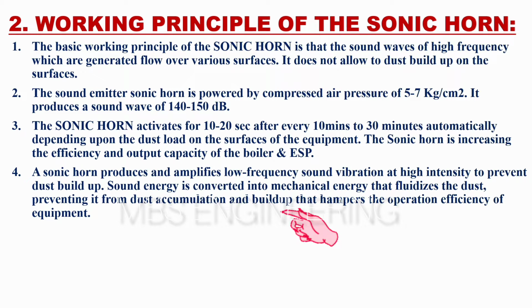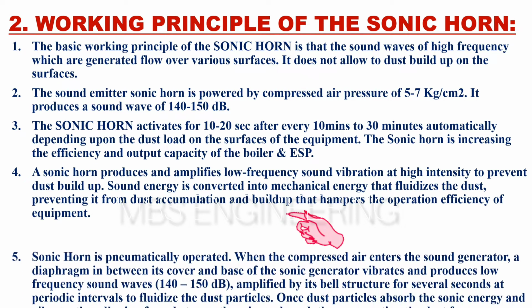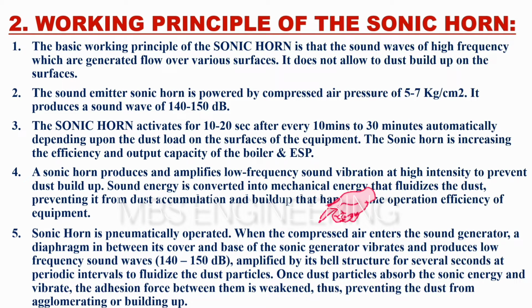Next, the fourth point, a sonic horn produces and amplifies low-frequency sound vibration at high intensity to prevent dust buildup. Sound energy is converted into mechanical energy that fluidizes the dust, preventing it from dust accumulation and buildup that hampers the operation efficiency of equipment. Next, the fifth point, sonic horn is pneumatically operated. When the compressed air enters the sound generator, a titanium diaphragm in between its cover and base of the sonic generator vibrates and produces low-frequency sound waves, 140 to 150 decibels, amplified by its bell structure for several seconds at periodic intervals to fluidize the dust particles. Once dust particles absorb the sonic energy and vibrate, the adhesion force between them is weakened, thus, preventing the dust from agglomerating or building up.